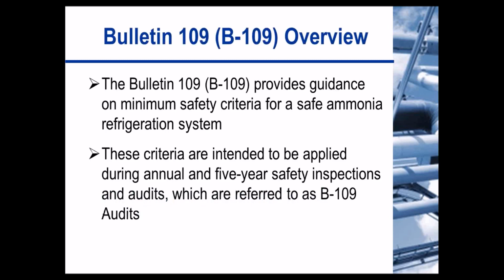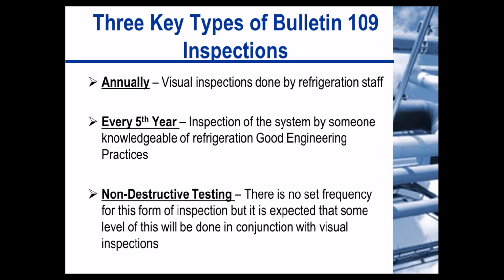So a quick overview, B109 provides guidance, as we said, on the minimum safety criteria for ammonia refrigeration systems. These criteria are intended to be applied during annual and 5-year safety inspections and audits, and these are collectively referred to as the B109 audits. Annual inspections are primarily done by refrigeration staff. And we've seen that one good practice is to have new personnel participate in these annual inspections as part of on-the-job training. Here we get to instill a sense of awareness of safe operating requirements.